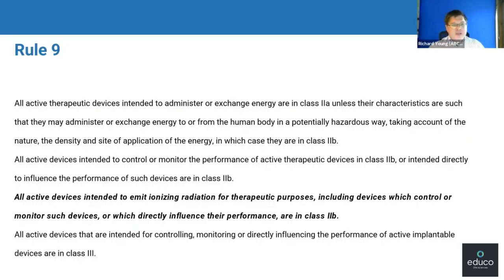Once we've done that, we get into active devices. And active devices are a very interesting area. And it says all active therapeutic devices intended to administer or exchange energy are class 2A, unless their characteristics are such that they may administer or exchange energy to or from the human body in a potentially hazardous way, taking into account the nature, density, and site of application of the energy, in which case they're class 2B. So rule 9 is the first one where you're being asked to make a judgment about how risky the application of your product is.